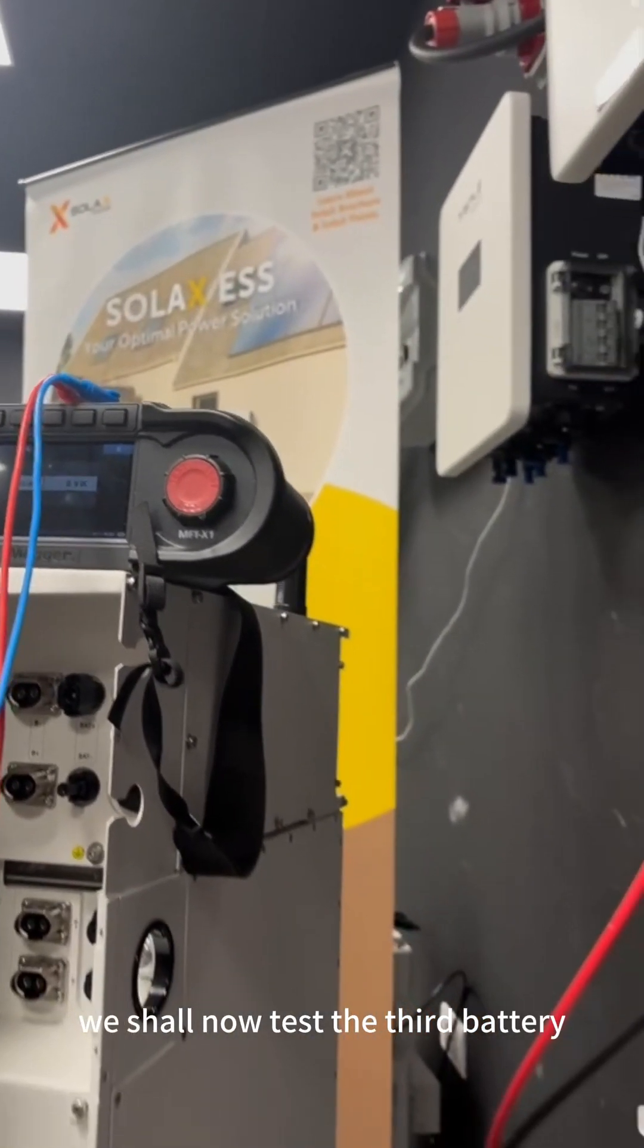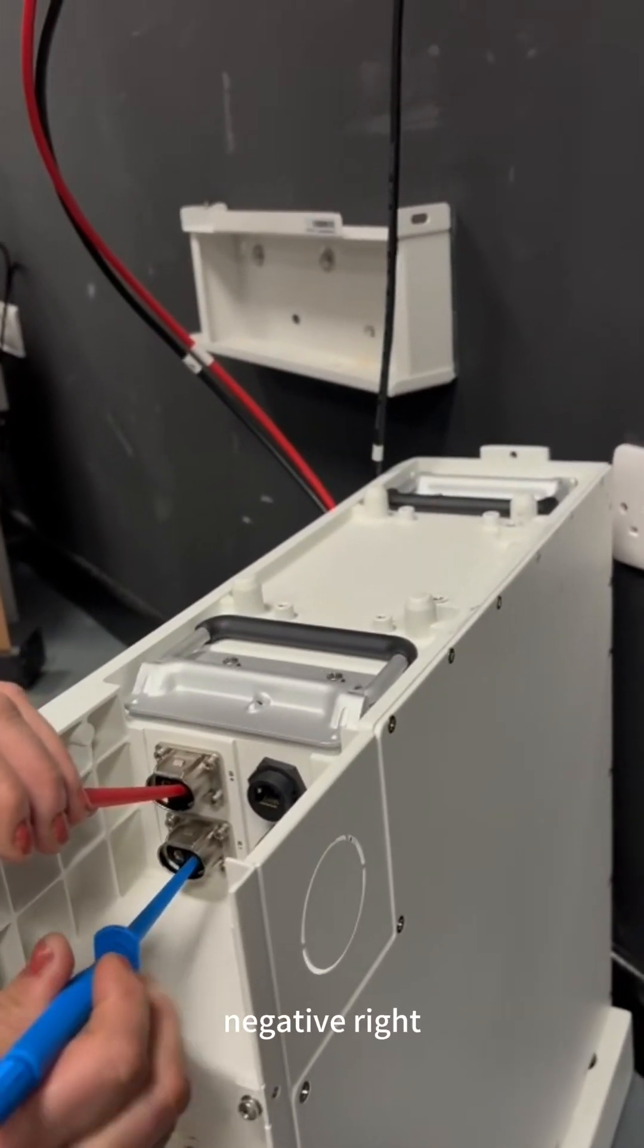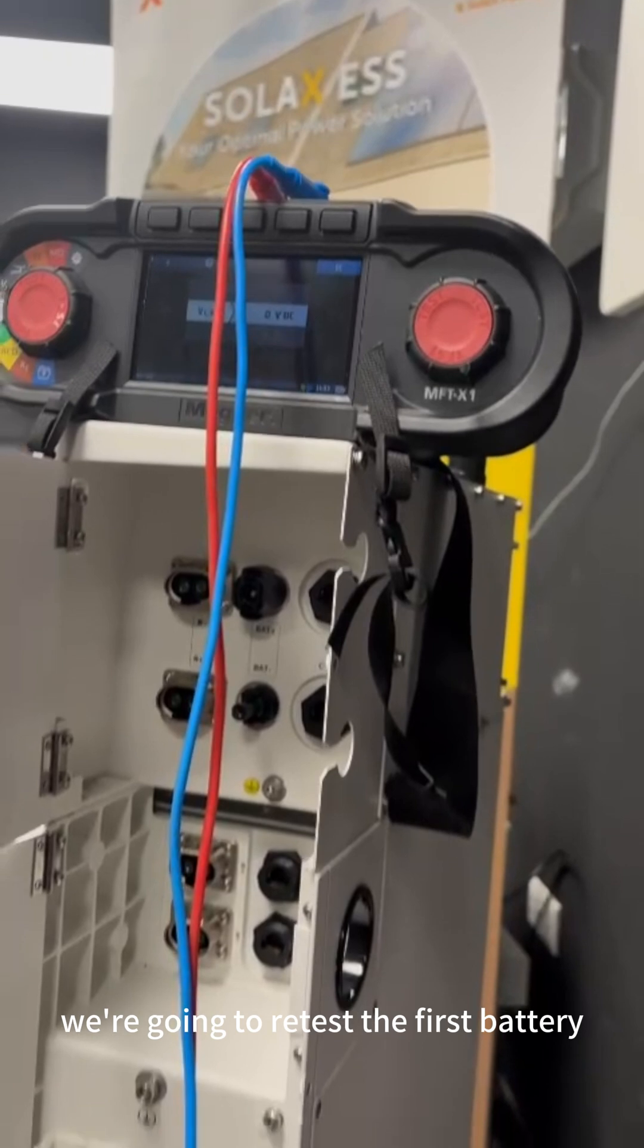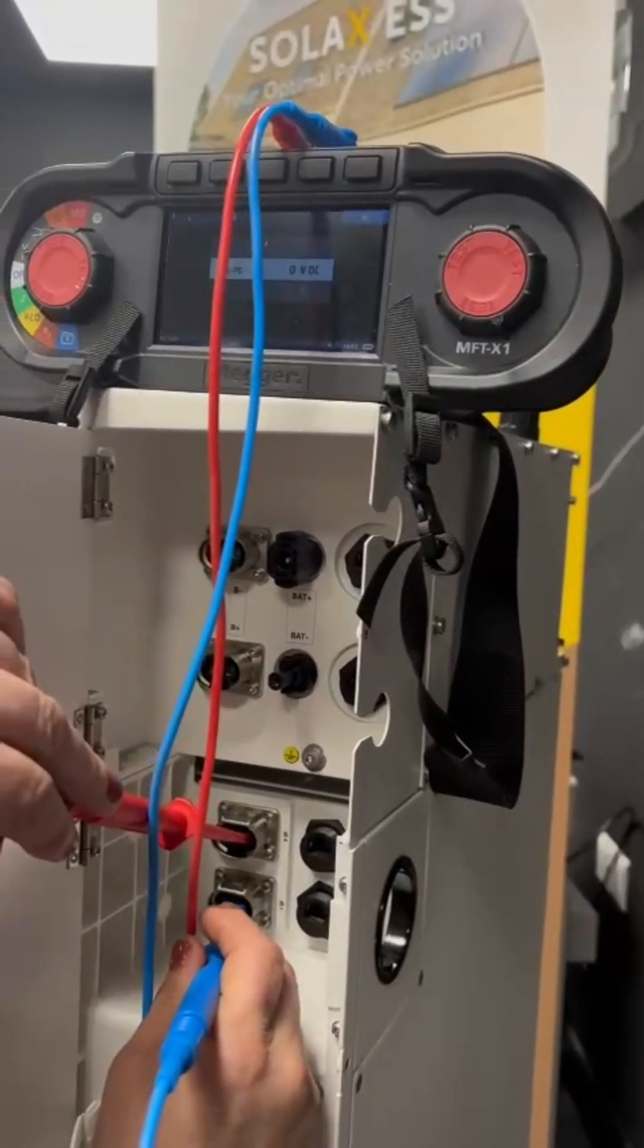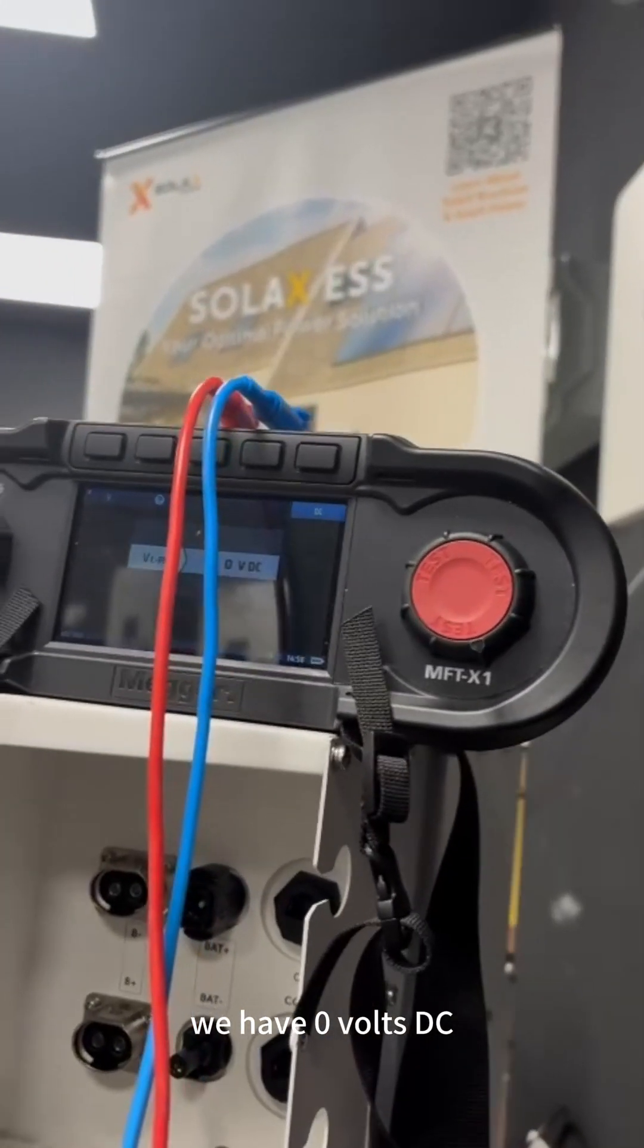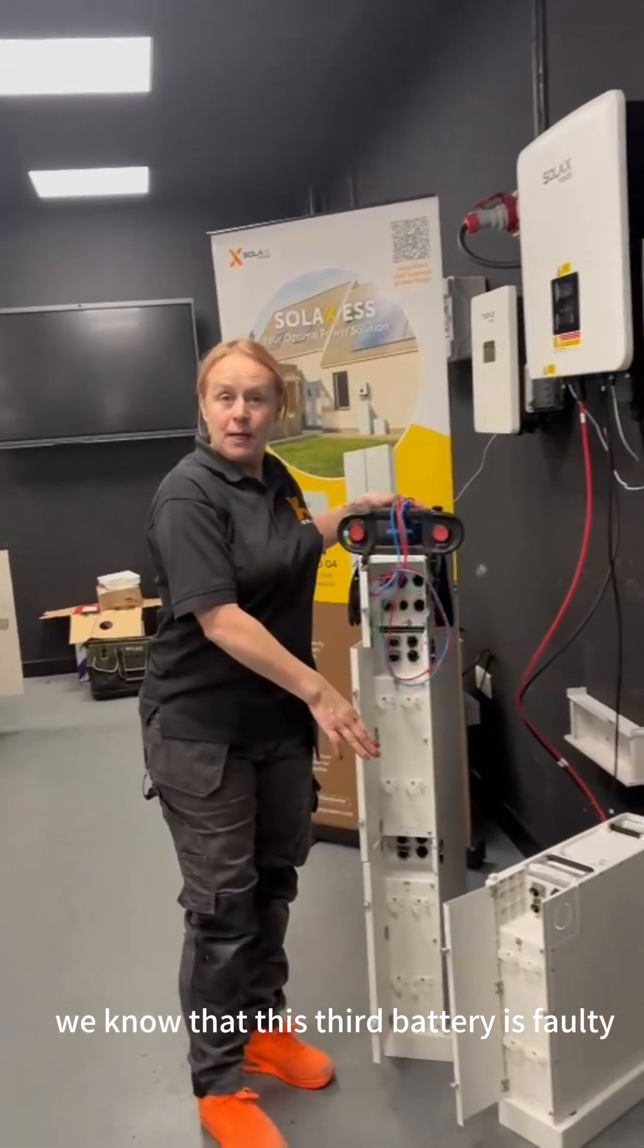We shall now test the third battery. Positive right, negative right. And on the tester, we have zero volts. Just to make sure our tester is OK, we're going to retest the first battery. Positive right, negative right. 105 volts DC. And back to the third battery, just to verify. Positive right, negative right. As you can see, we have zero volts DC.